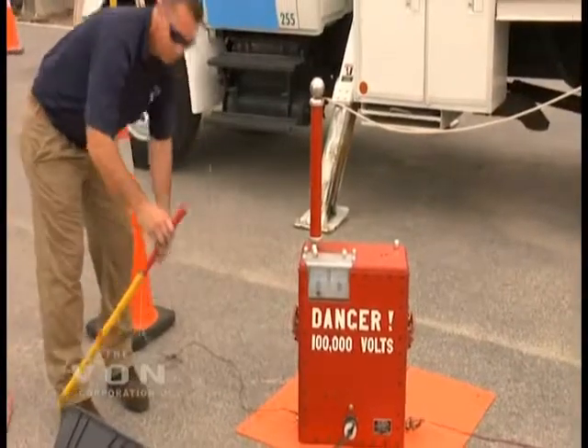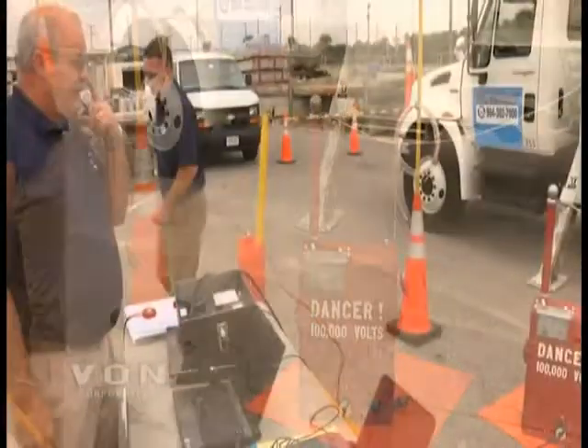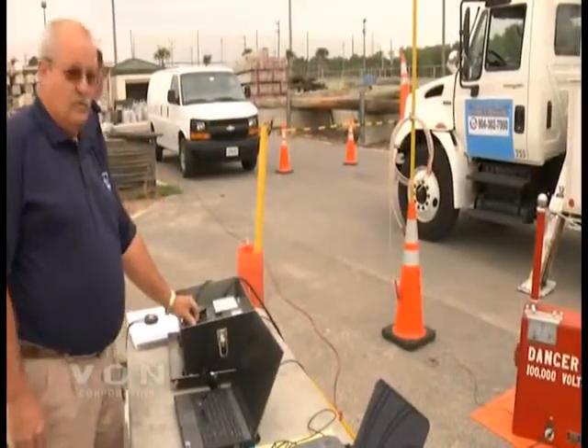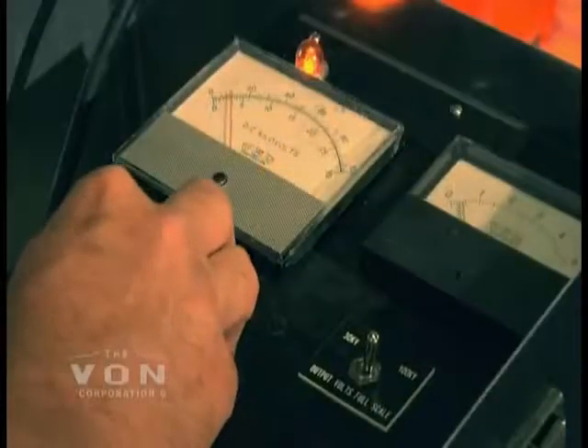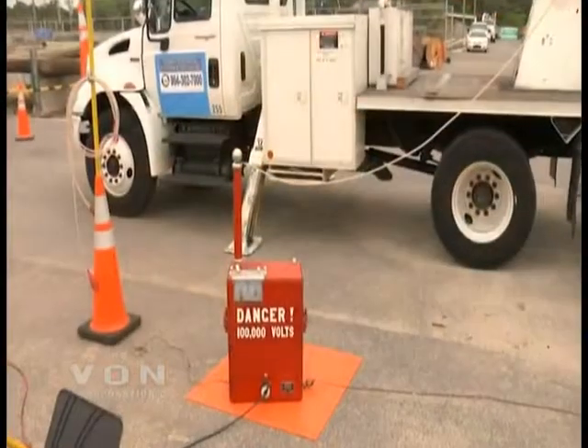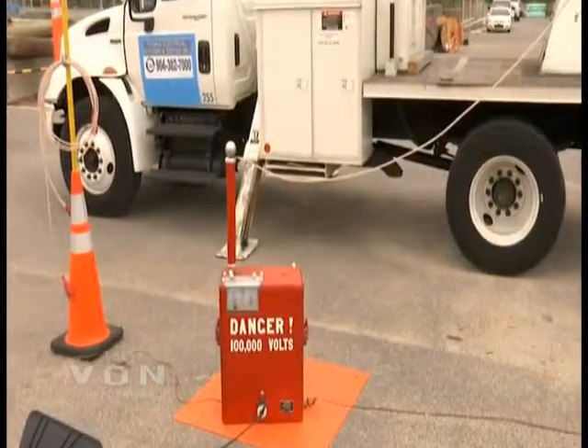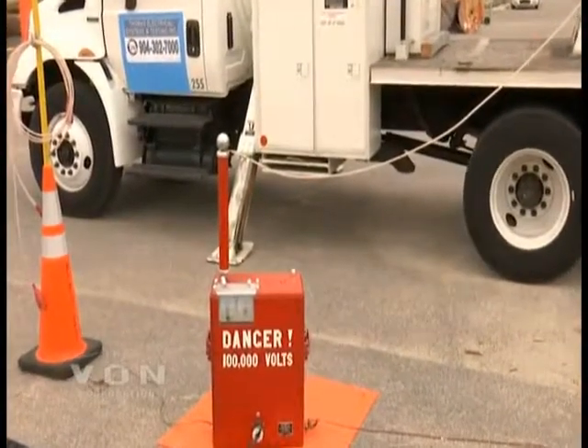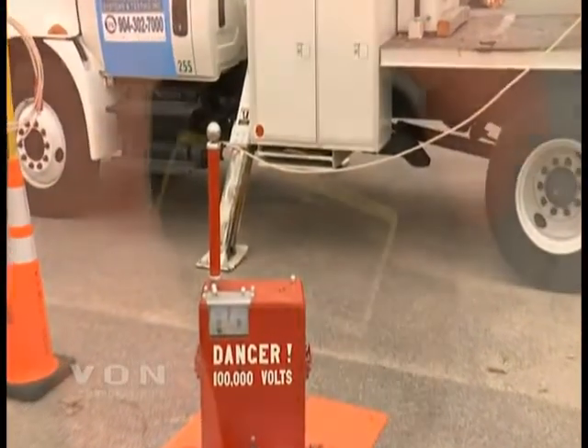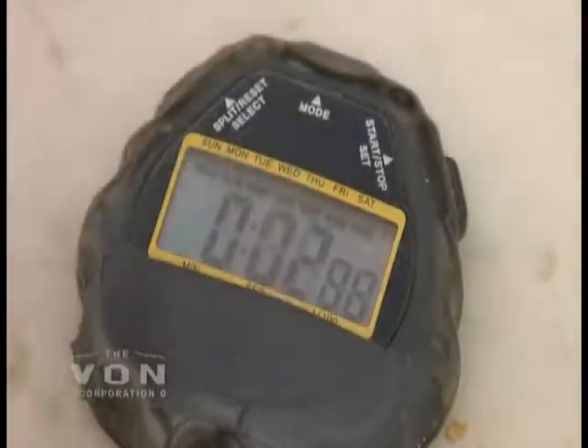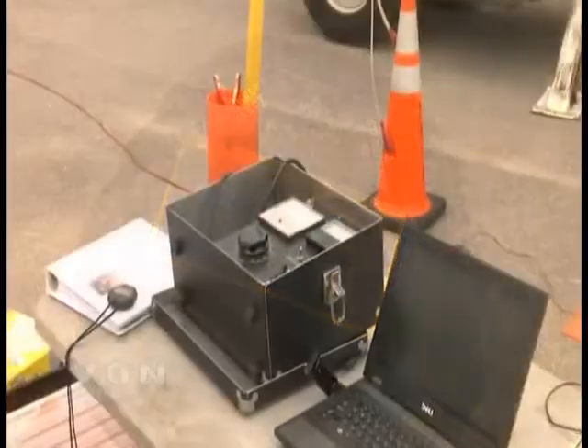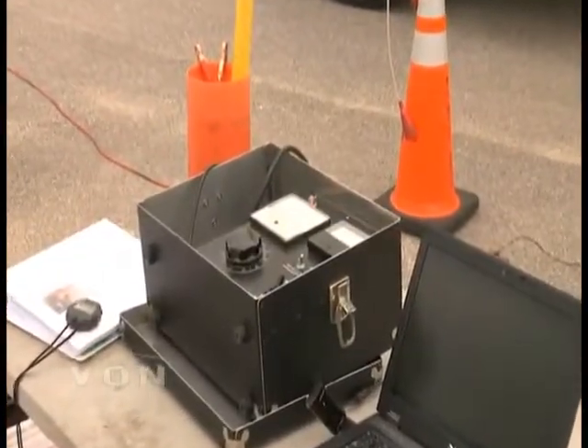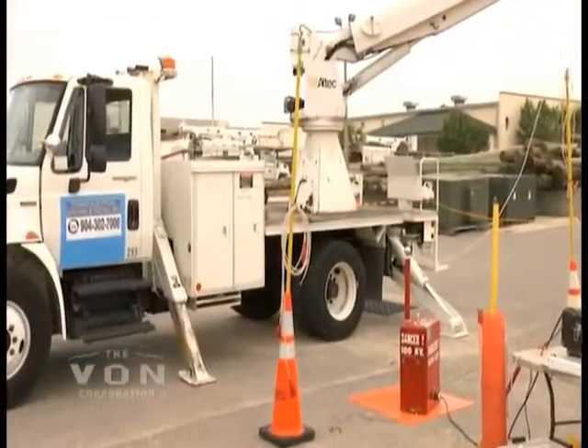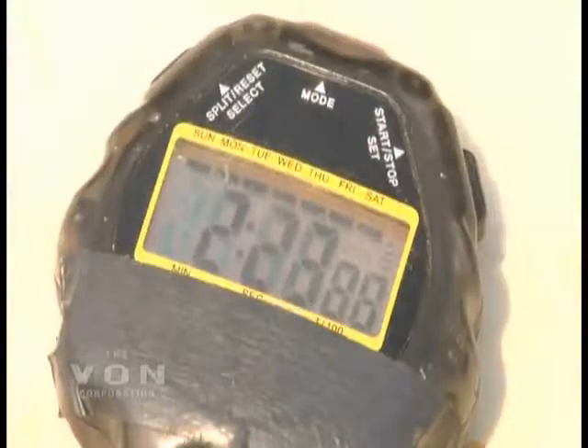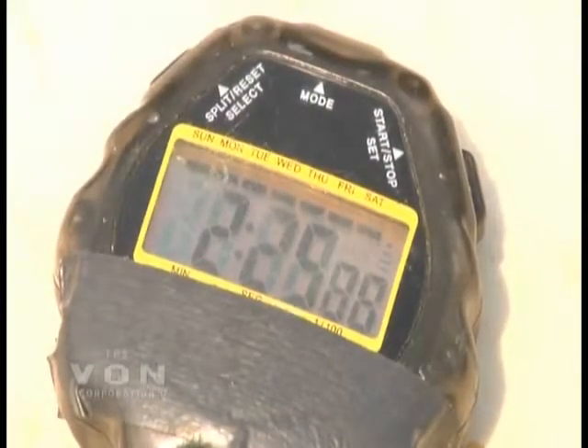And with everybody in the clear, we're going to turn our machine on and start raising our voltage. We are now at 56,000 volts. Our microamps are less than 30 microamps, and we start our stopwatch. The VON unit takes very little power. You can actually hook it up to a converter on your vehicle and operate the machine off of a converter, so you don't have to carry a generator with you to operate this unit.